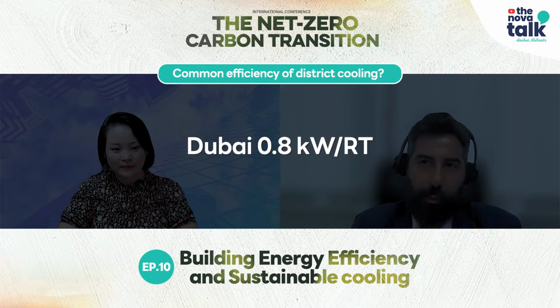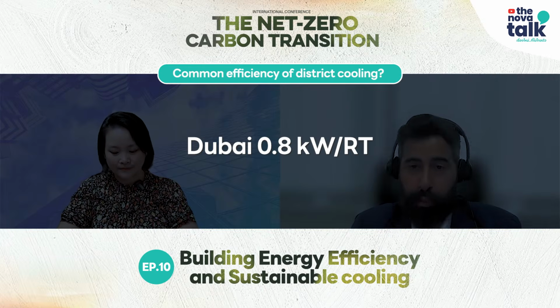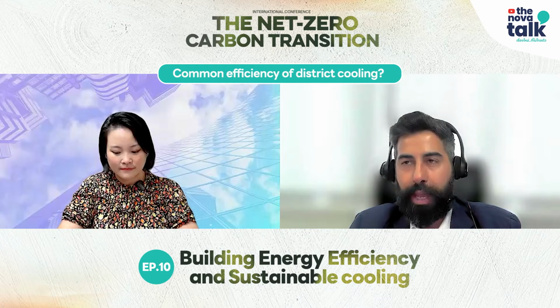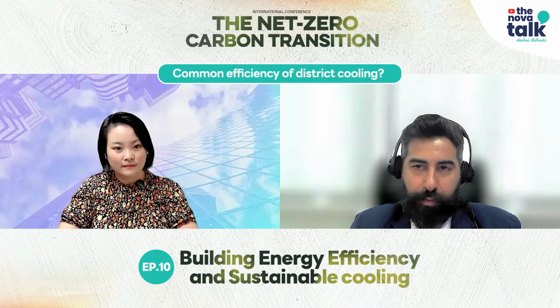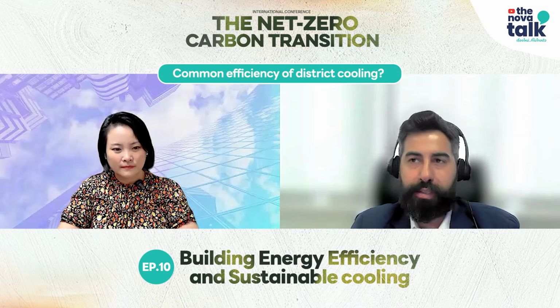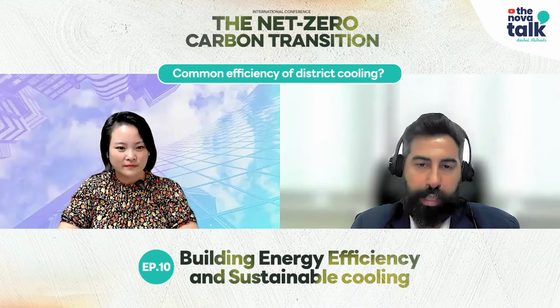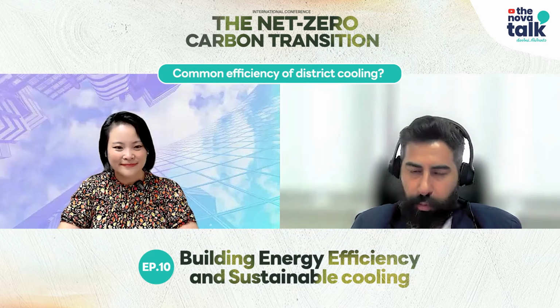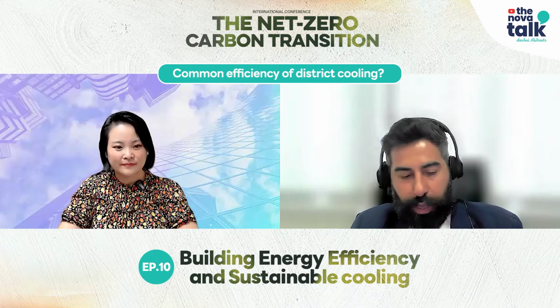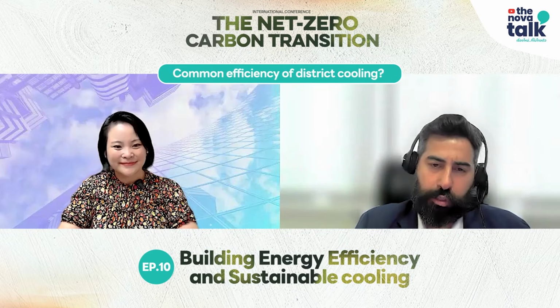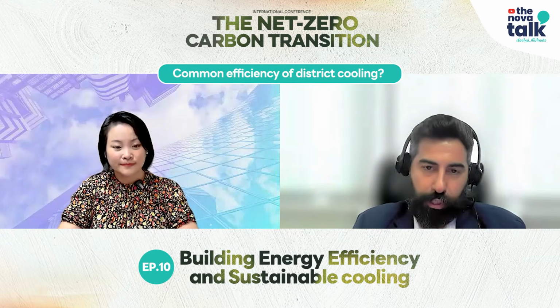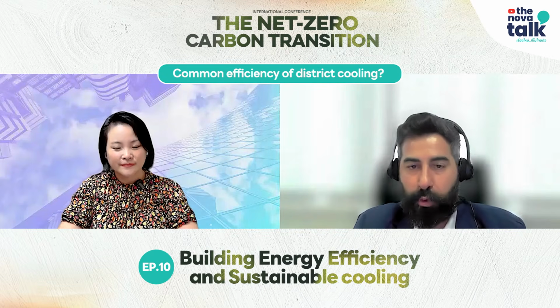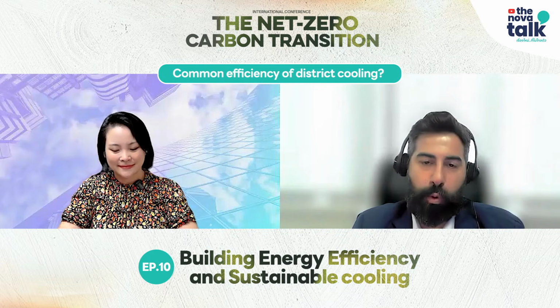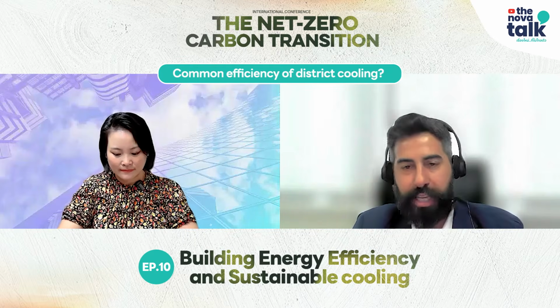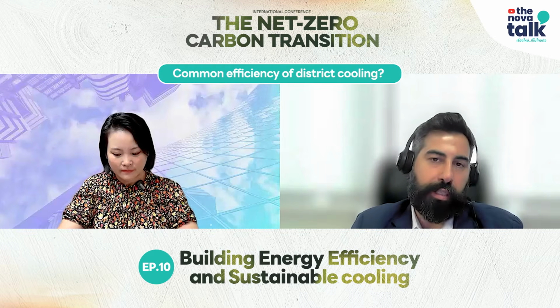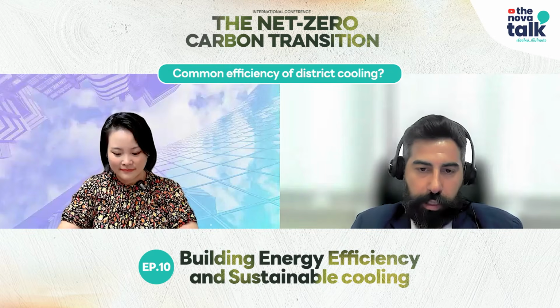So for example, in Dubai, we're able to get to 0.8 kilowatt hour per ton hour on average annual. And let's say in other places, maybe a little bit lower when we have a lower wet bulb. So probably I would say in Thailand, you should still be able to get 0.85 kilowatt hour per ton hour, or maybe lower. And that depends also on the load profile. If you have thermal energy storage on site or not, if you have VFDs on the chillers, and how is the load profile? So the load profile is very important to dictate what would be the ultimate kilowatt hour per ton hour. But I'd say a 0.85 should be something that is achievable with the current technology.